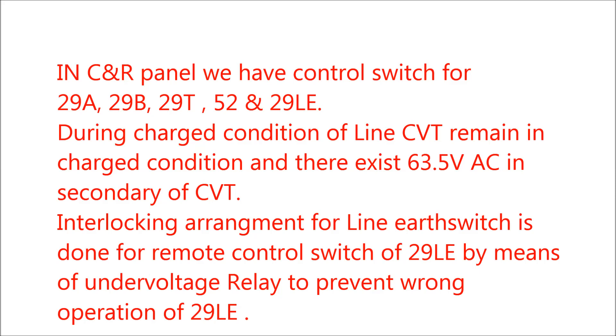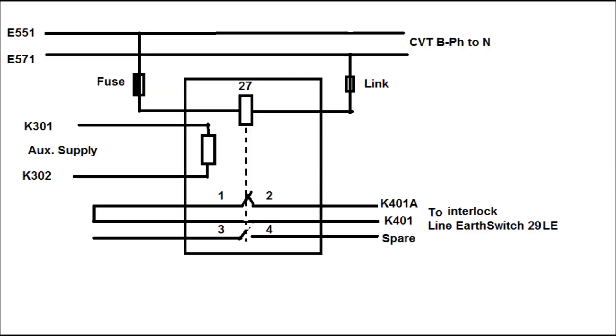The interlocking arrangement for the line earth switch is done for the remote control switch of 29LE by means of the under voltage relay, to prevent any wrong operation of 29LE. That is, it is expected that during a charged condition we cannot operate 29LE. The diagram for the under voltage relay has been shown in this figure.